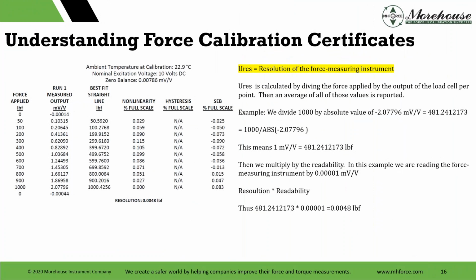We have resolution. I like to say resolution because people ask, how do you calculate a load cell's resolution? Here's a very easy example. You take the capacity point or the force point, and you divide by the value at that point. You don't have to take the absolute value, it's just recommended because at some point you're going to have to do it, or you can call it negative, whatever. In any case, take the 1,000 applied over here. We take the applied force, and then we come over here and ask, what did the load cell read at that applied force? And we look at it.